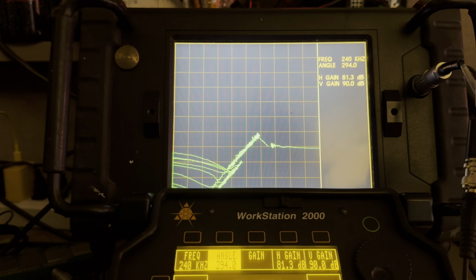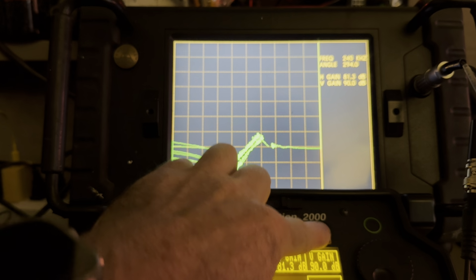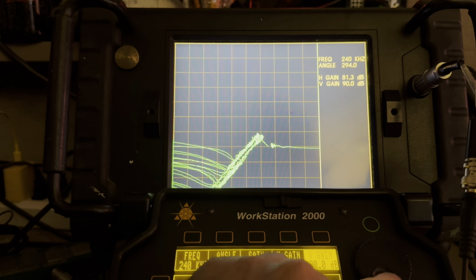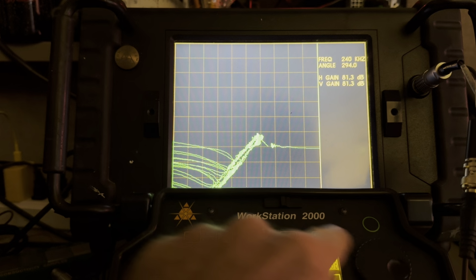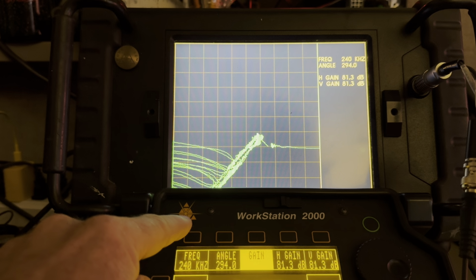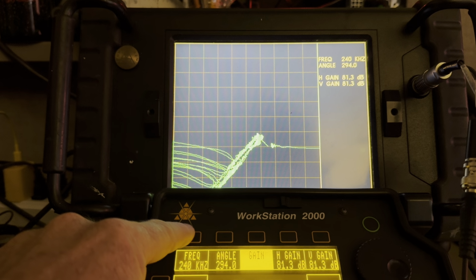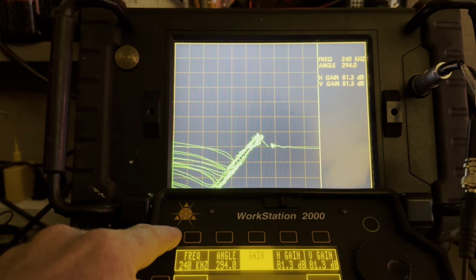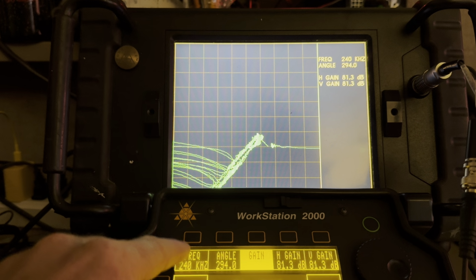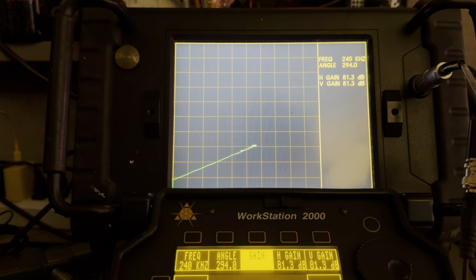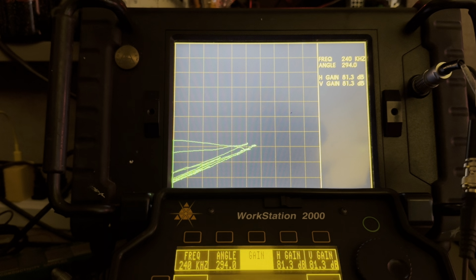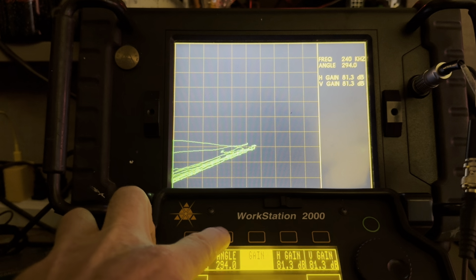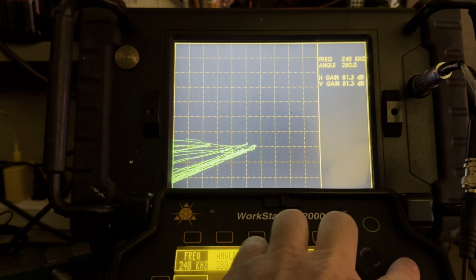Well, I can see some flaws in there, but the gain seems to be a little bit too hot, and I noticed that my horizontal and vertical gain are not the same. So I'm going to adjust those 2 values so they're the same - starting with a normal aspect ratio for horizontal and vertical gain. Hit the erase button - well, could have been how I was holding my probe. My liftoff is not quite flat, so I'm just going to adjust that up a little bit again.